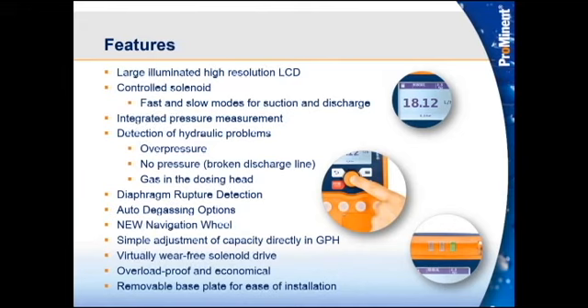Integrated pressure measurement. Our competition pumps have built-in pressure switches in the head of the pump, which could potentially see chemical attack. Our pump is going to, when we program it here at the factory, we put the programming in. The pump creates an energy profile, very similar to what the Delta did, if you're familiar with that. So we no longer have a switch of any type. We create an energy profile.